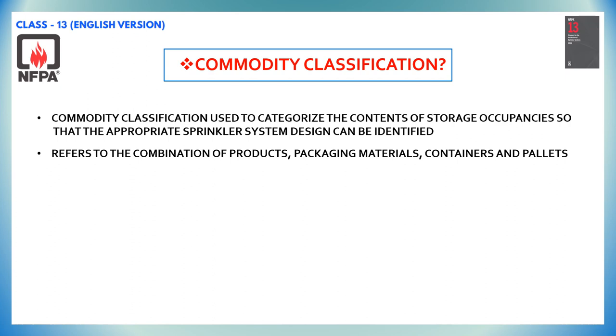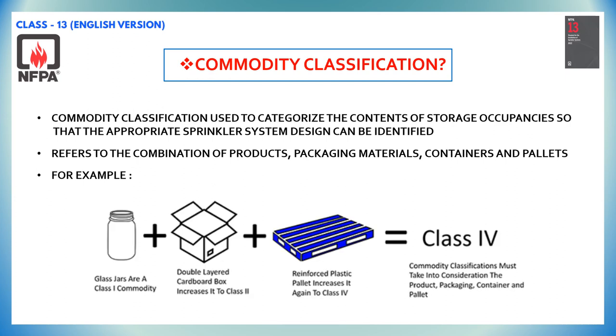In order to understand this, let us have a look at an example. We have glass jars stored in a double-layered cardboard box with cardboard dividers, and it is sitting on a reinforced plastic pallet. Even though the glass jars are only a class 1 commodity, the cardboard box and plastic pallet increases the fuel load so that it should be considered a class 4 type.